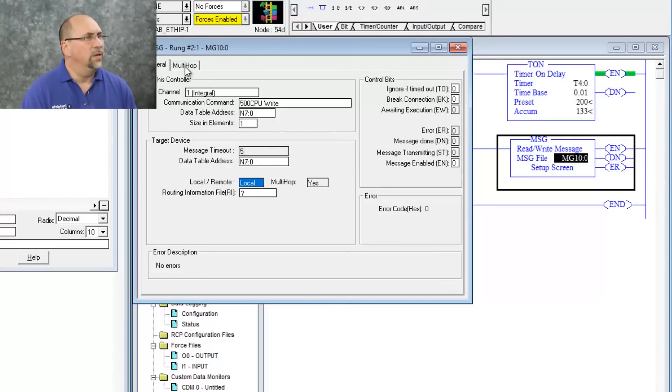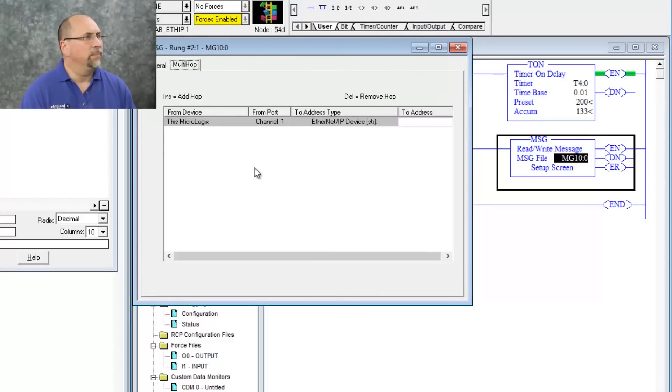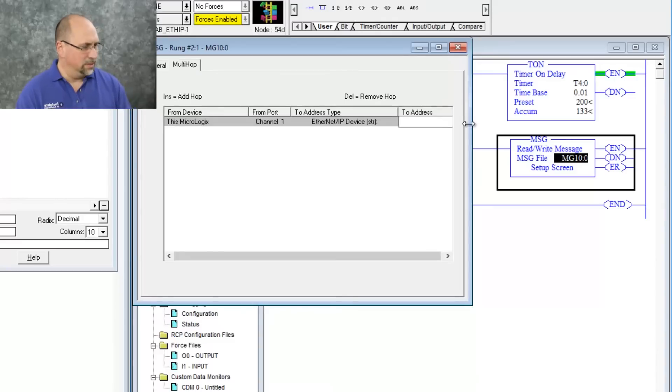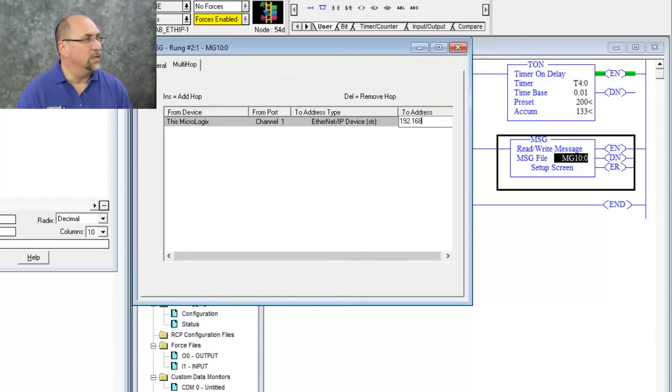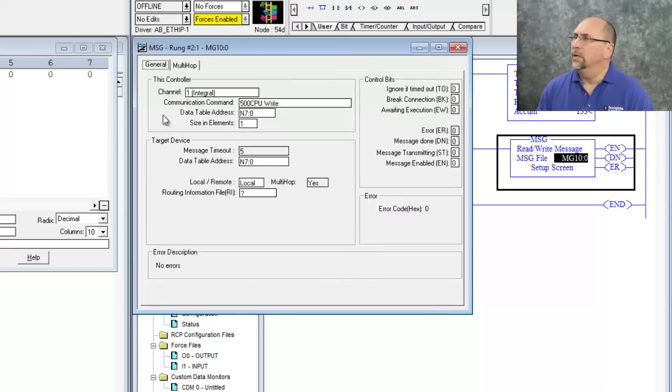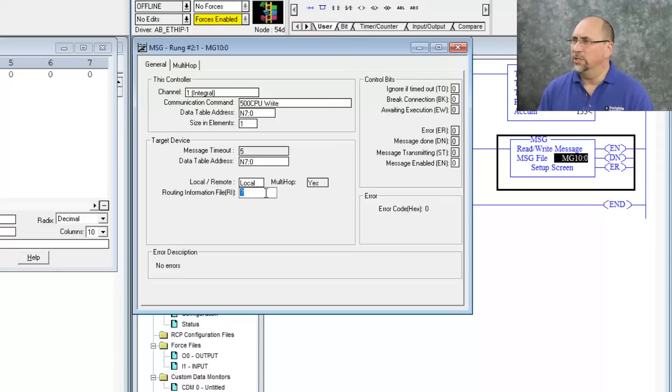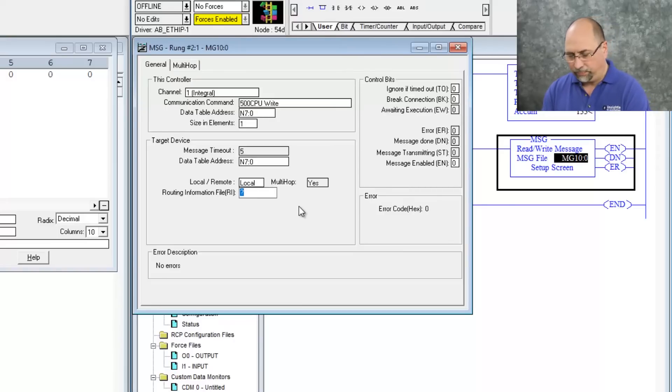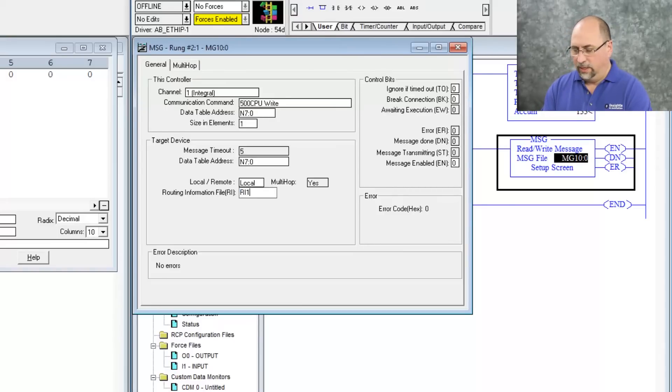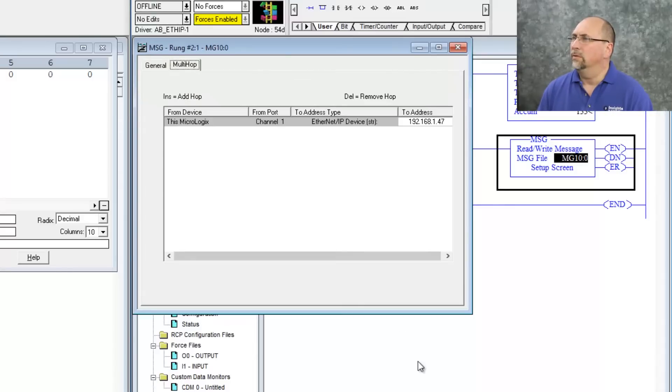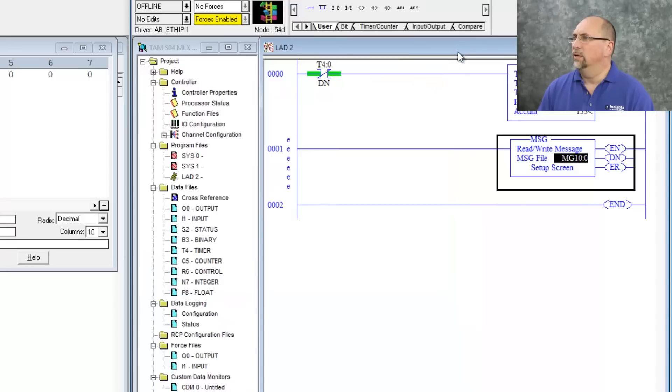And let's go over here to multi-hop. We'll give that remote PLC an address of 192.168.1.47. That's what my 505 is set to. And now it wants a routing information table. So let's go ahead and give that RI11:0. Okay. So everything's done here.